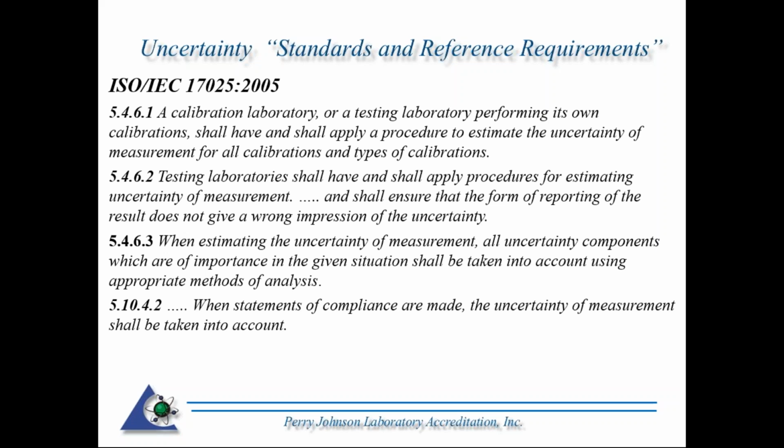One thing in 5.4.6.1, it specifies testing labs. So if you're a testing lab and you're performing your own calibrations, let's say, for example, you have analytical balances and you decide, I am going to just calibrate these in-house. That's what we're talking about here. So if you're performing your own calibrations to support your testing at PJLA, we call this in-house calibration, you too have to have a procedure and estimate the uncertainty for this measurement.